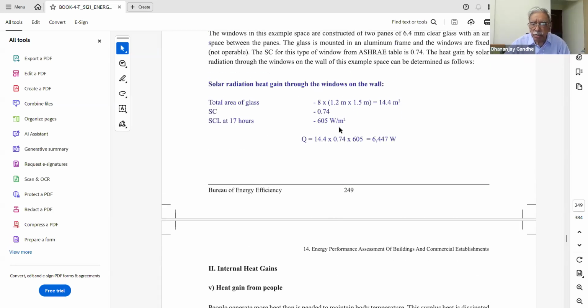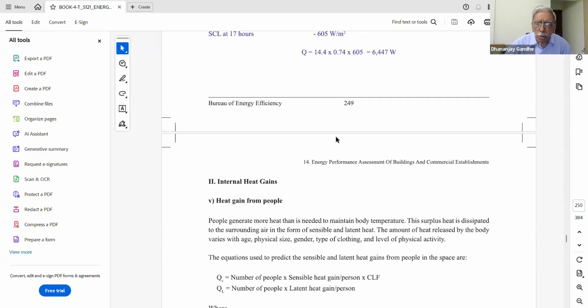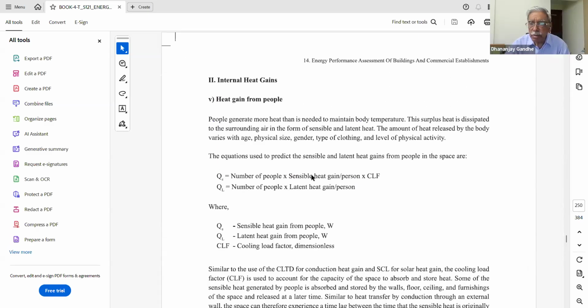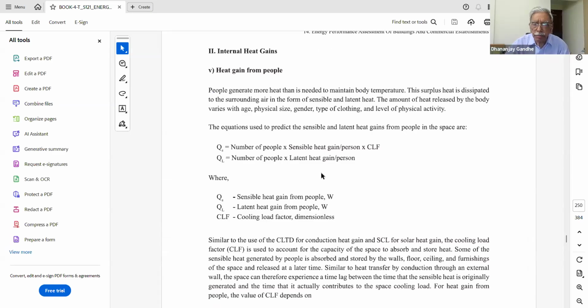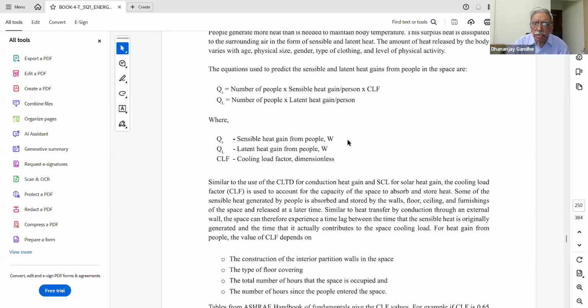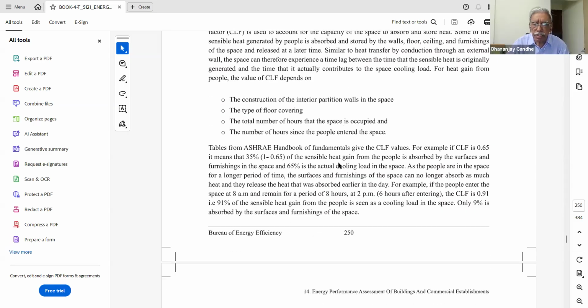Also, what is the radiation gain? These calculations are given over here. Okay, so these are the external loads. The internal load heat calculation is using basically the heat gain from the people. There is the number of people, and the latent heat and sensible heat per person. So the latent heat of people is also there. That is the number of people multiplied by the latent heat per person. These are standard figures which are taken from ASHRAE. This is 75 watts sensible heat per person. This is 55 watts per person.